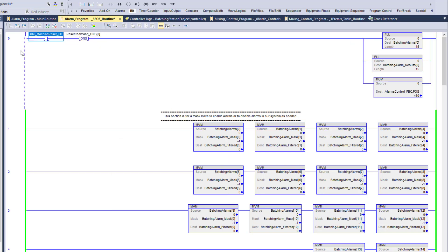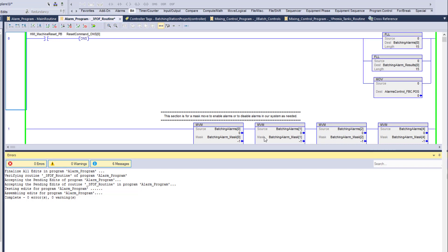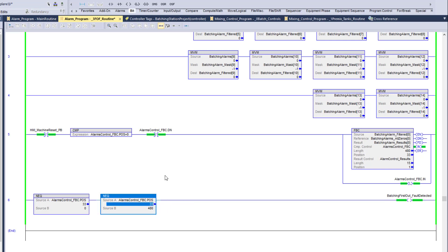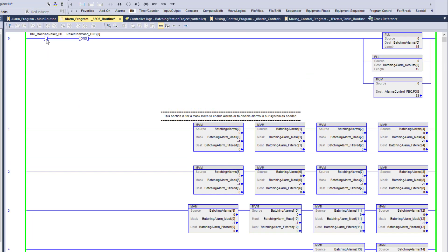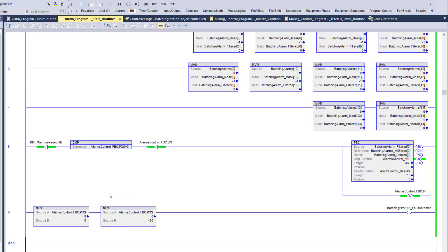Now if we get a fault — say we force this bit to a one — we have a fault, the position reads 33, and a fault is detected. We don't have full alarming or ALMDs set up yet; this is just the catch where you're detecting the first one to come through the pattern. When we hit the reset button, everything resets and goes back to working.